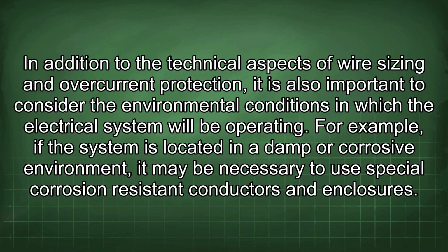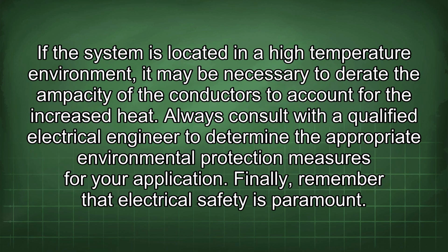In addition to the technical aspects of wire sizing and overcurrent protection, it is also important to consider the environmental conditions in which the electrical system will be operating. For example, if the system is located in a damp or corrosive environment, it may be necessary to use special corrosion-resistant conductors and enclosures. If the system is located in a high-temperature environment, it may be necessary to derate the ampacity of the conductors to account for the increased heat. Always consult with a qualified electrical engineer to determine the appropriate environmental protection measures for your application.